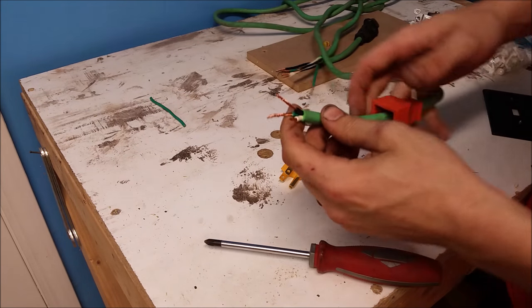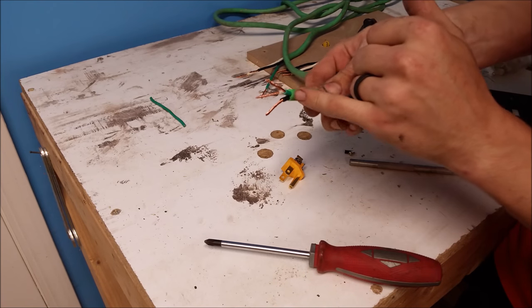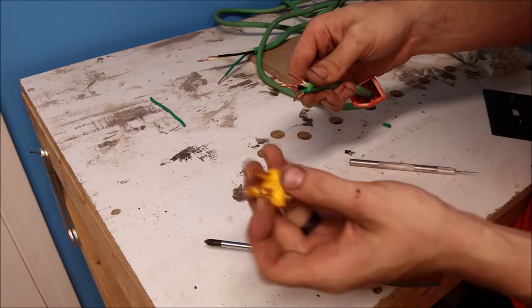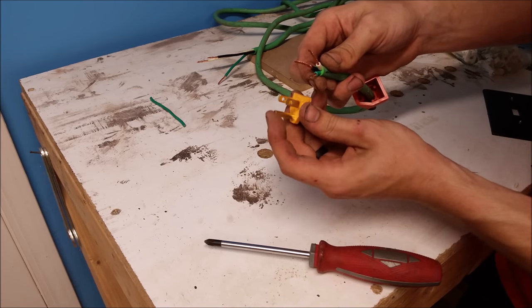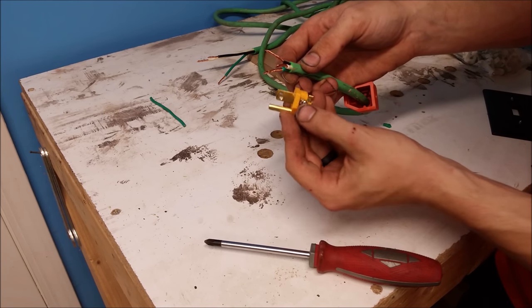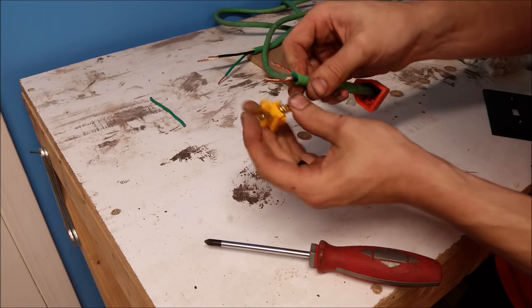Now we're just going to connect all our wires to the plug. The black is the hot, the green is the ground and the white is the neutral. So on our plug we should have a little green screw on the grounding plug. That's where the green wire goes. We should have a white wire with a silver screw and we should have the hot wire, the black, goes to the brass screw.